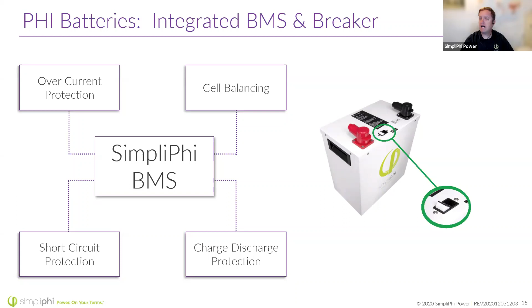All of the batteries also have a built-in breaker that you can see here. And this gives an extra level of overcurrent protection. But it also is an added level of safety when it comes to installing the battery. You can turn the battery off essentially, make all of your connections so you're not seeing any arcing on the battery wires. You're not worried about shorting out the battery terminals with your wrench, with your torque wrench, I hope, because we want to torque these down properly. So it's a nice feature to be able to turn the battery off and turn it back on, as well as give that overcurrent protection.